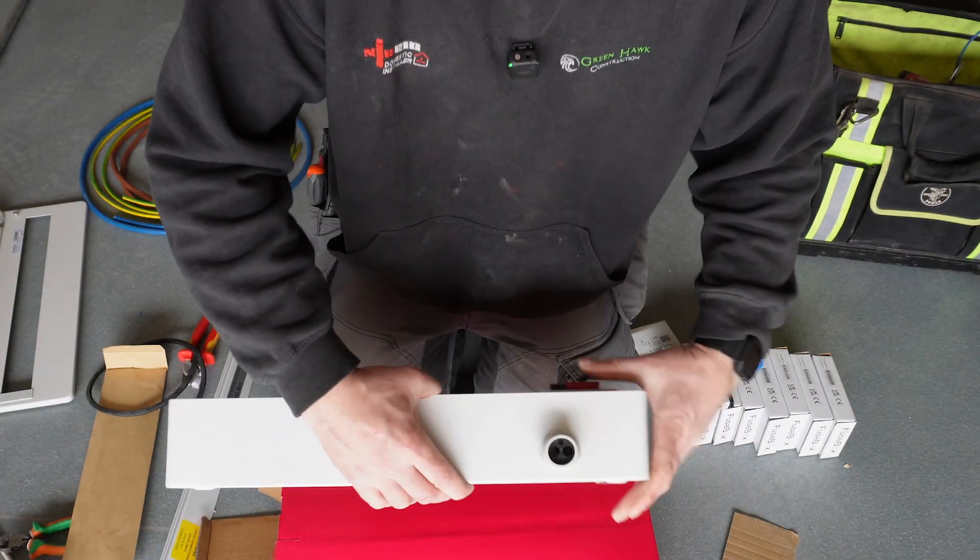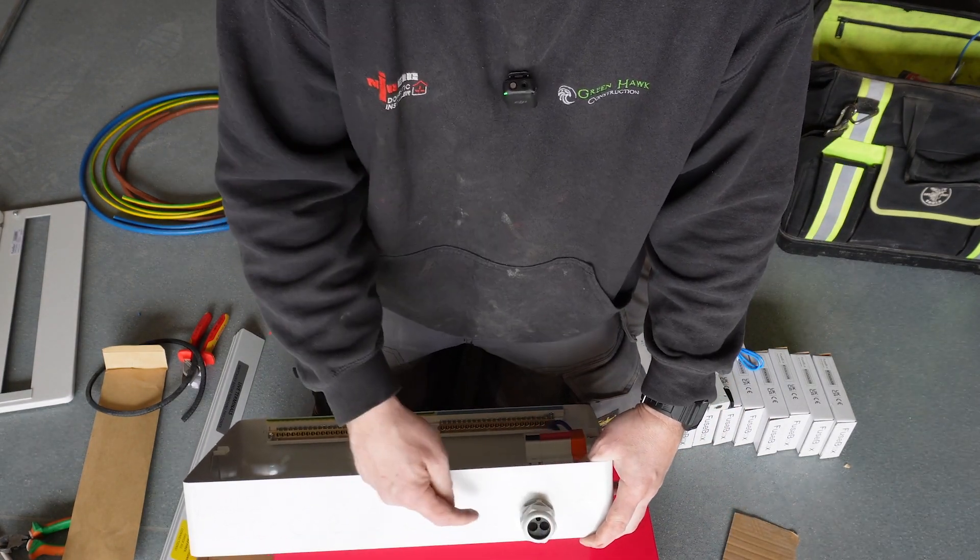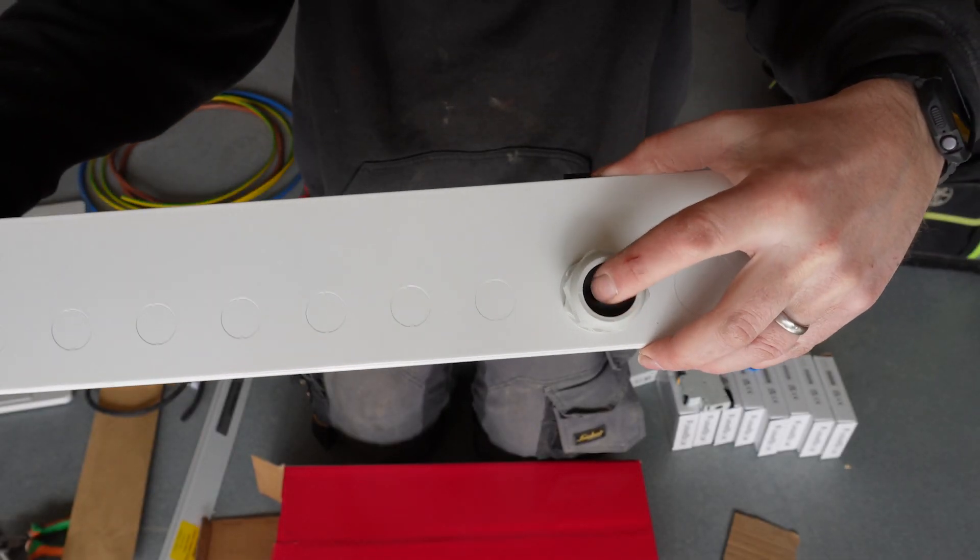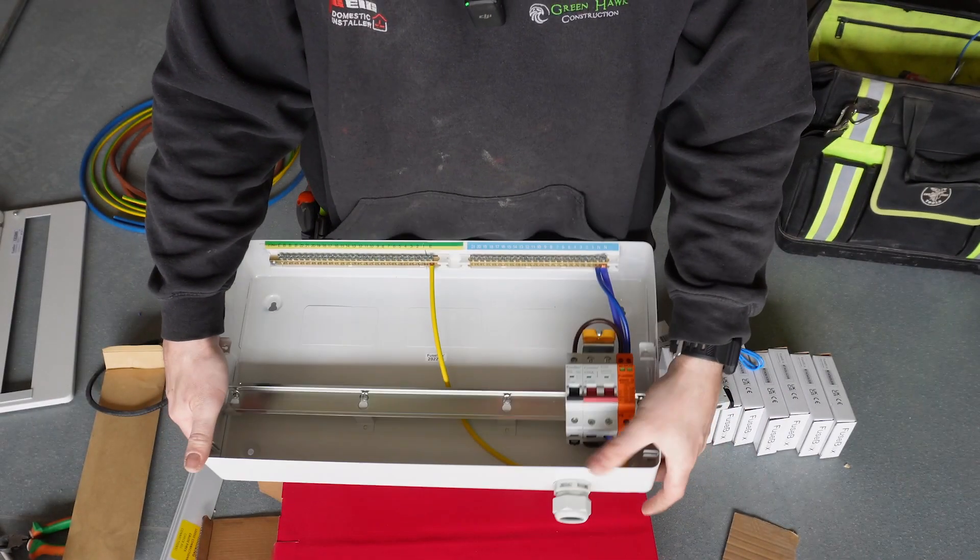What you want to do is make sure that the two larger holes on the actual gland inside are towards the back, because once you've done that, the meter tails are tucked behind the DIN rail a bit easier.